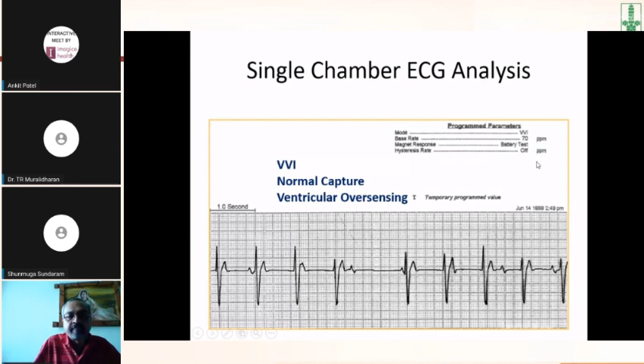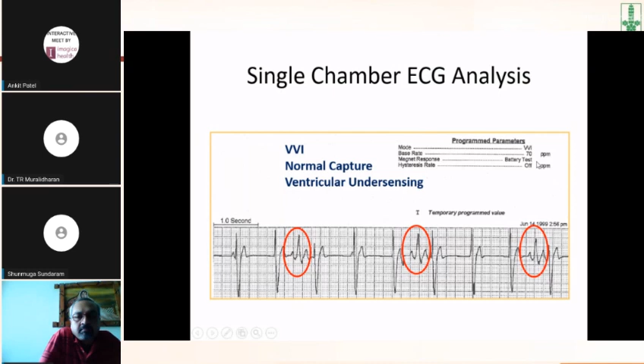We see again program parameters, base rate at 70, magnet response is there, and see pacing spike up at 70 beats per minute, and then those are the sensed events. So normal capture, but ventricular undersensing, it just goes on firing at will. Next.